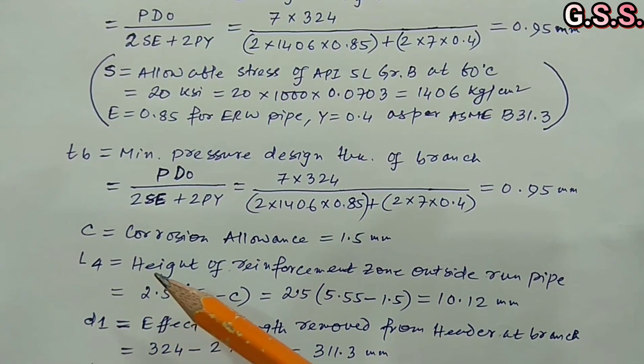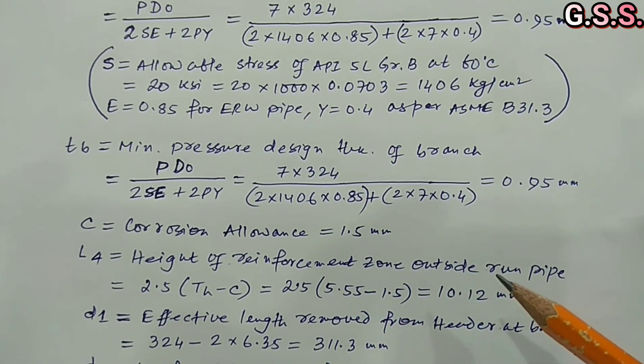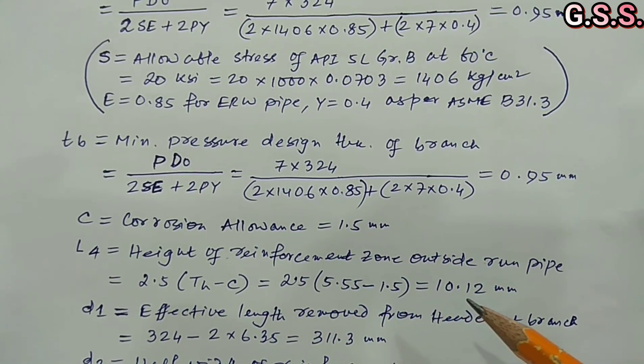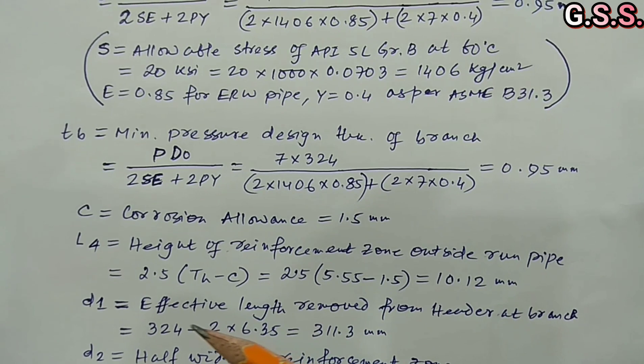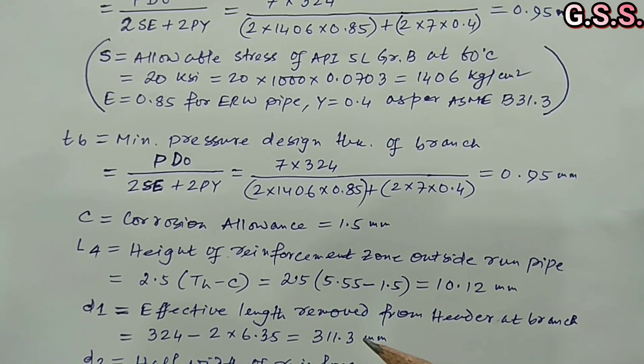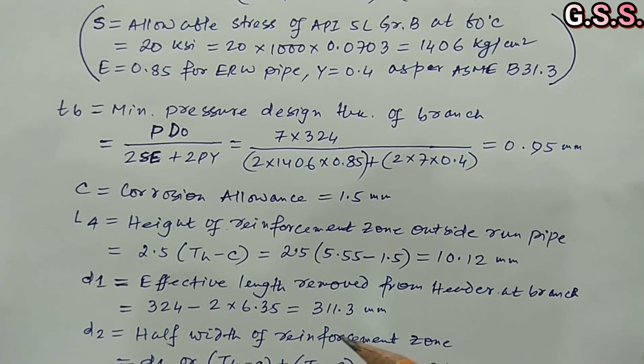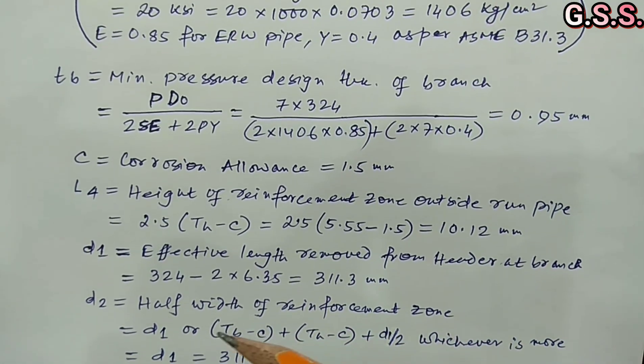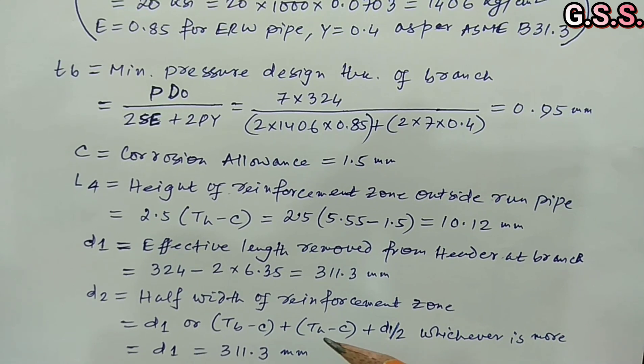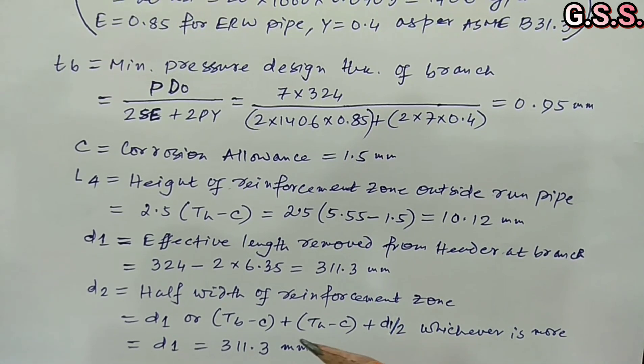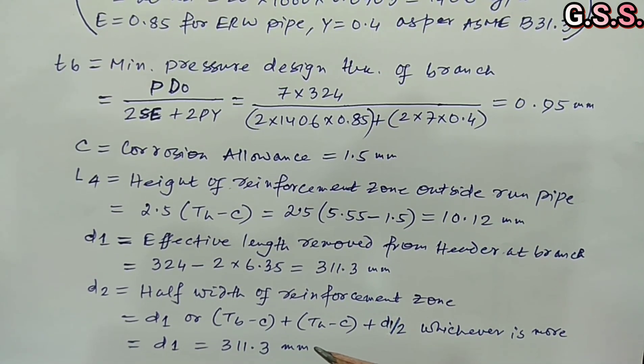Capital L4 = height of reinforcement zone outside run pipe = 2.5 × (capital TH − C) = 10.12 mm. Small D1 = effective length removed from header at branch = branch OD − 2 × branch thickness = 311.3 mm. Small D2 = half width of reinforcement zone = the greater of small D1, or (capital TB − C) + (capital TH − C) + (small D1 / 2), giving D2 = D1 = 311.3 mm.